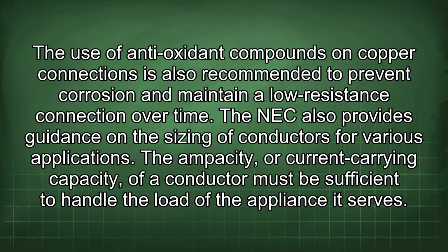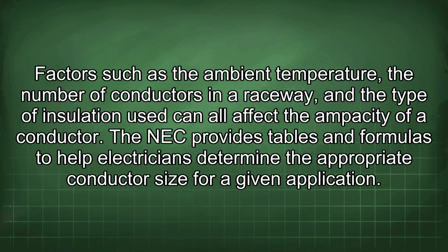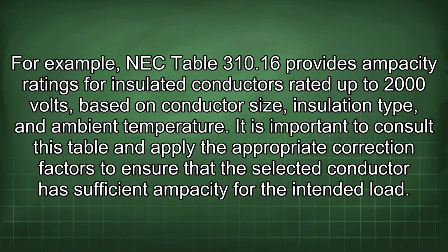The NEC also provides guidance on the sizing of conductors for various applications. The ampacity, or current carrying capacity, of a conductor must be sufficient to handle the load of the appliance it serves. Factors such as the ambient temperature, the number of conductors in a raceway, and the type of insulation used can all affect the ampacity of a conductor. The NEC provides tables and formulas to help electricians determine the appropriate conductor size for a given application. For example, NEC Table 310.16 provides ampacity ratings for insulated conductors rated up to 2000 volts, based on conductor size, insulation type, and ambient temperature. It is important to consult this table and apply the appropriate correction factors to ensure that the selected conductor has sufficient ampacity for the intended load.